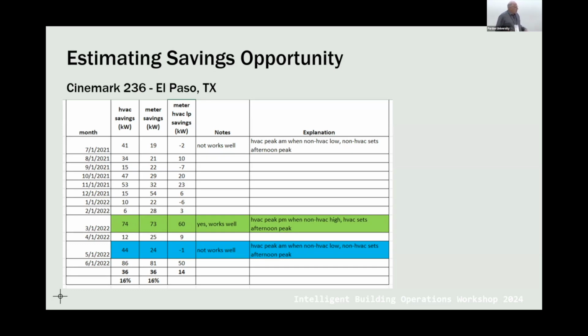The other interesting point I was trying to make is: how coincident are the HVAC peaks with the building peaks? Because if you're not looking at the building's total energy use and you're just deploying through the thermostats — which is commercially attractive — we initially assumed the HVAC peaks align well with the building peaks. It turns out that it varies a lot.